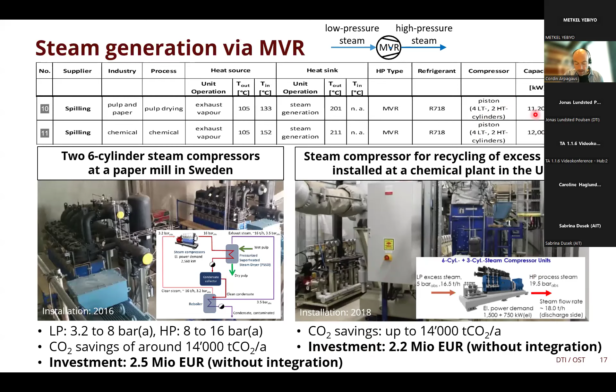The COP, which was 5.3, is based on the condensing heat and also the heat from the condensate cooling to 105 degrees. The special learning here is the optimization of the discharge pressures. If these could be reduced to lower pressures, then, clearly, the demand for electrical power can be reduced, and so the COP and efficiency of the system improve. The investments are in both cases around 2.2 to 2.5 million euros without the integration. The capacities, as I said, are 11 and 12 megawatt.